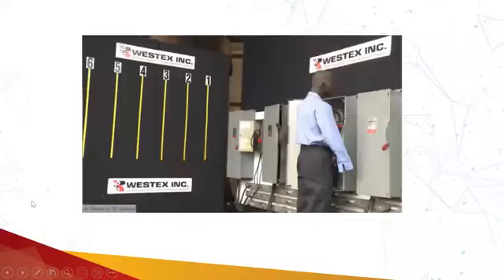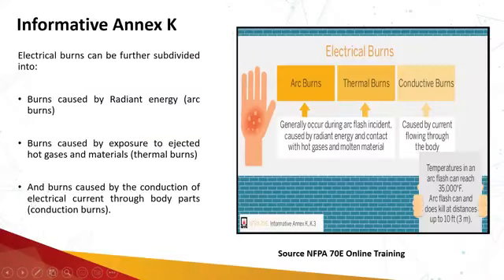So how can the shock hazard or the conductive burn be prevented? If we are working on a system which has been put into an electrically safe work condition, or if we are using shock protection PPE, then this shock hazard and the conductive burn can be eliminated. How about the arc flash burn and the thermal burns? These types of burn can also be eliminated if you are working on a system which has been put into an electrically safe work condition.